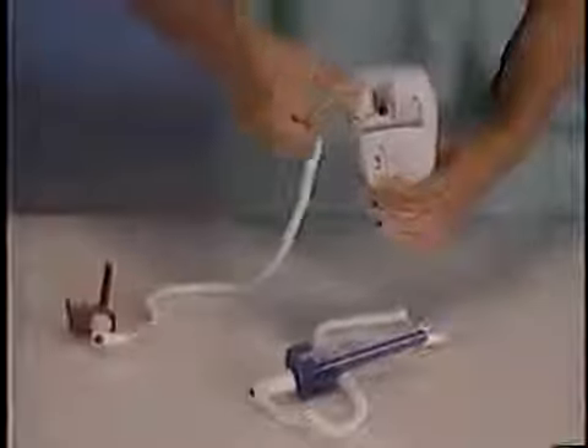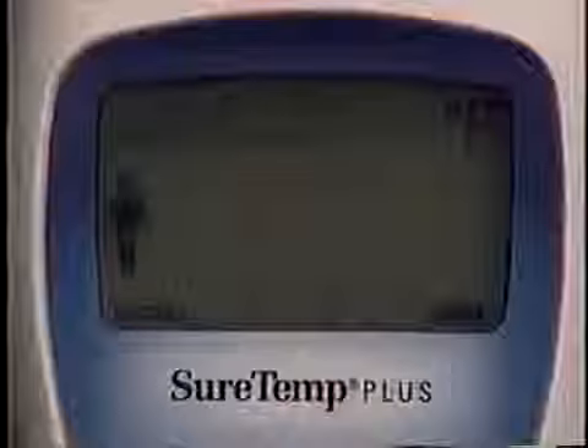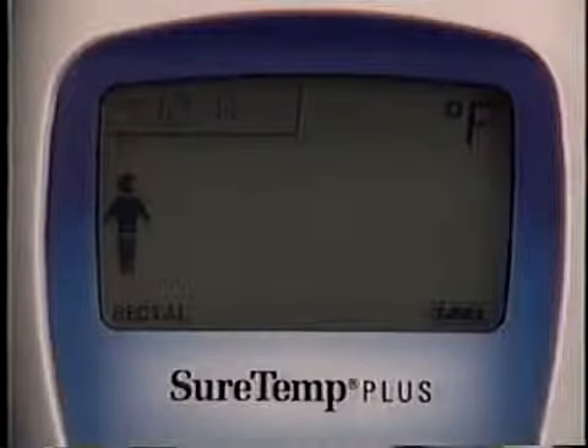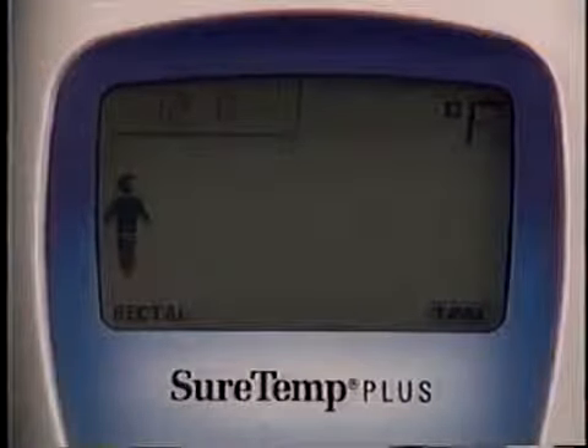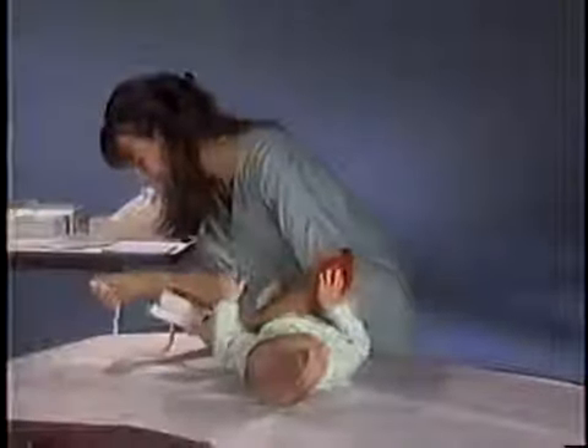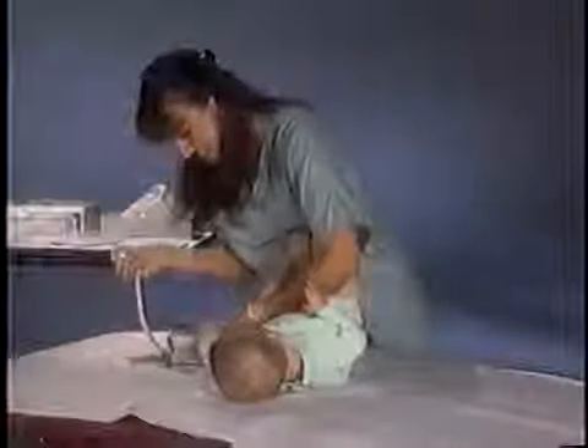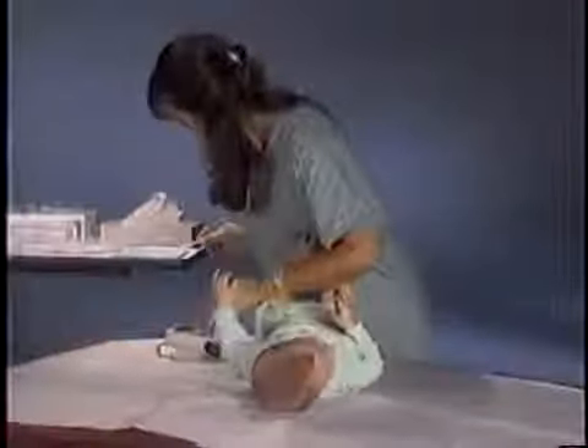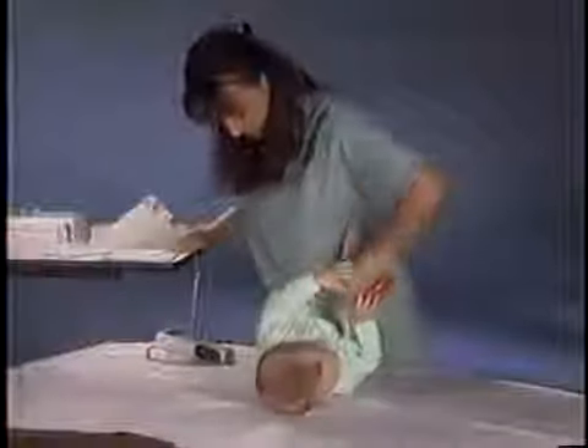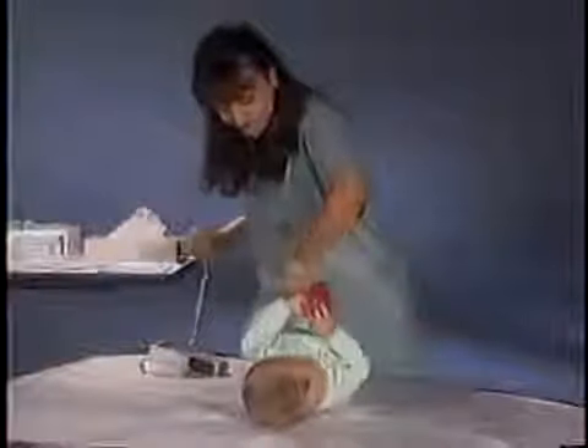Use the probe with the red ejection button and the red probe well when taking a rectal temperature. With the rectal probe and probe well installed, the thermometer only operates in rectal mode, and no other modes can be selected. To reduce cross-contamination, wear gloves and cover the probe handle with your gloved hand while taking a rectal temperature. Insert the probe into a probe cover and apply a thin coat of lubricant to the probe tip if desired.